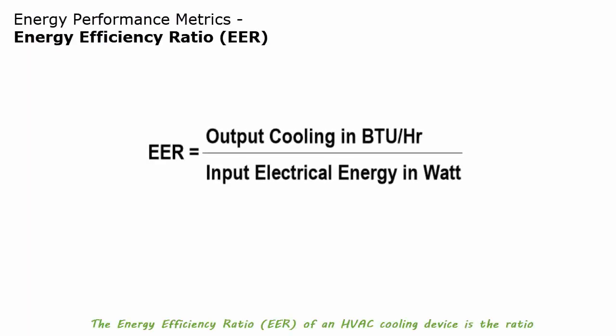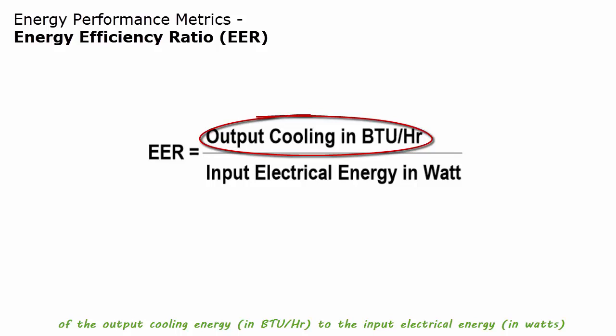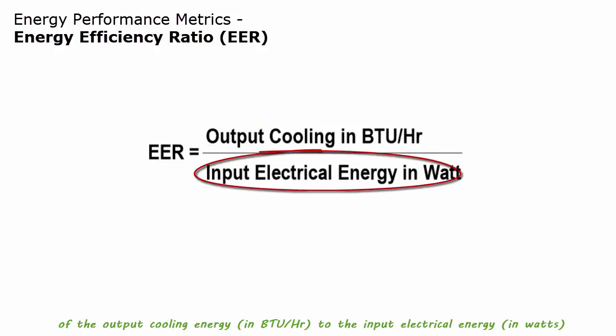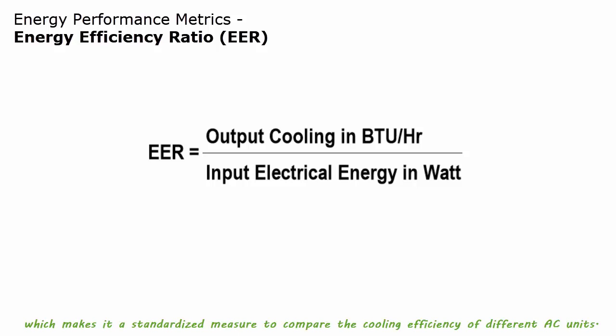The energy efficiency ratio, EER, of an HVAC cooling device is a ratio of the output cooling energy in BTU per hour to the input electrical energy in watts. At a given operating point, EER is normally calculated at an outside temperature of 95 degrees F and an inside temperature of 80 degrees F and 50% relative humidity. EER is an easy and accurate way to gauge how an AC unit will operate during the peak cooling time at 95°F outside. EER does not consider seasonal temperature changes, which makes it a standardized measure to compare the cooling efficiency of different AC units.